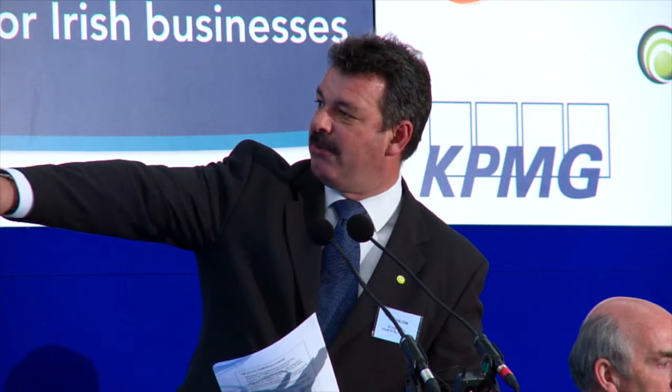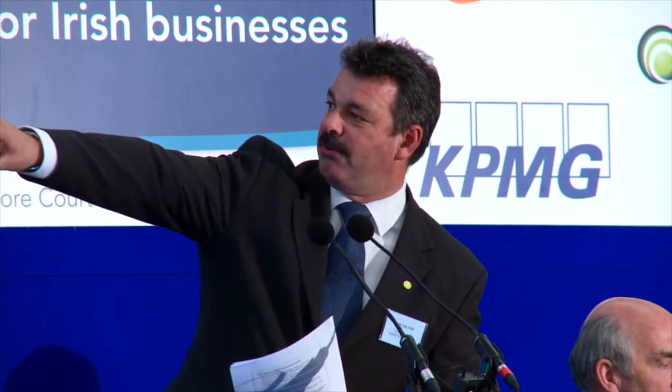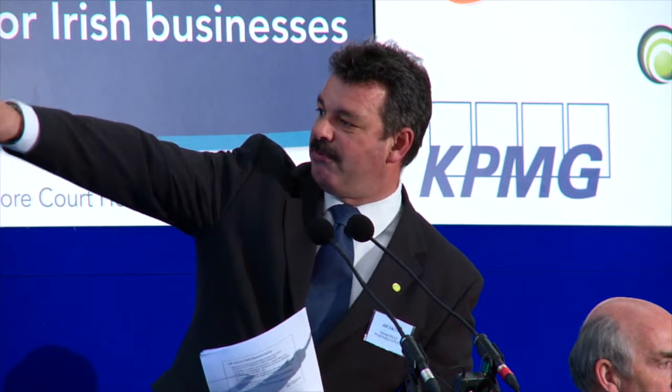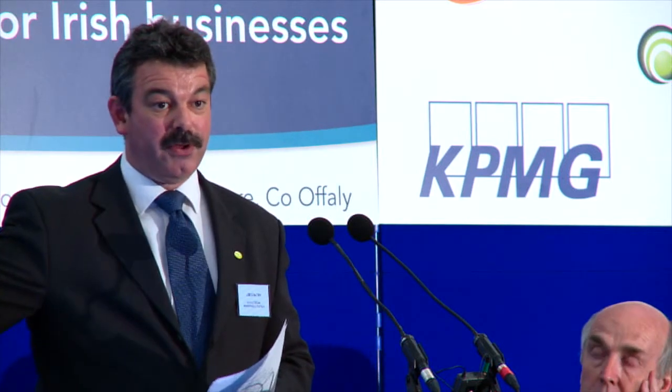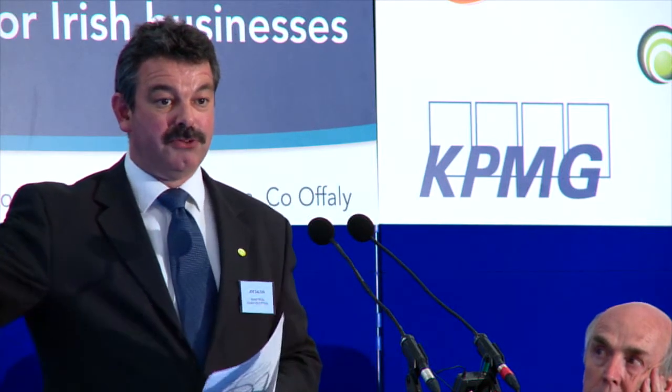You can see here that with those 400 turbines, we could have 5 or 6 events for the majority of days in a year. So for 60 or 65 days, we'll have 5 or 6 events. And each one of those events will have to be responded to by an operations and maintenance team, which will typically be 2 or 3 people. And if we're going to do this like a power station, we want the response to be reasonably quick. We don't want a machine to fail on Friday evening at 5 o'clock and for us to be waiting around until Monday morning at 9 o'clock for somebody to respond to that. We'll need them to be available to do that work.